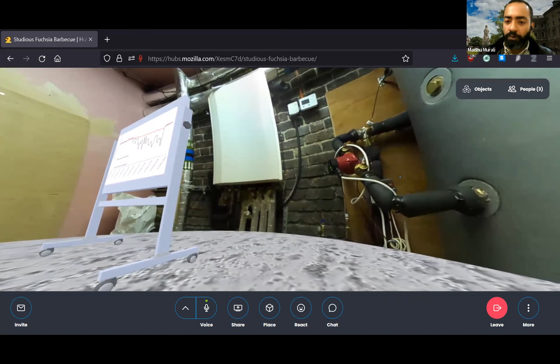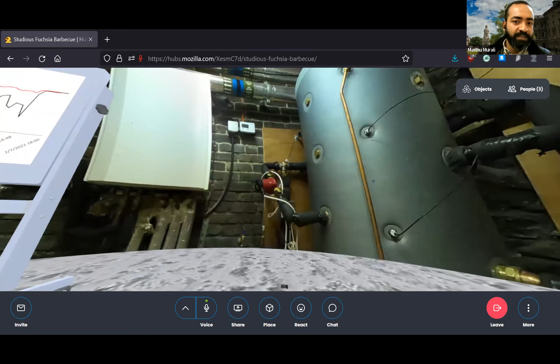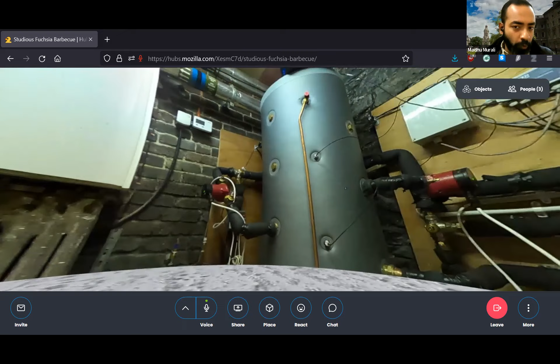Basically, what happens in this system is that the heat from the wastewater is always absorbed and put into the buffer tank. But the buffer tank isn't a completely necessary part of the system. It was more of a trial in this case to see whether the buffer tank improved the situation and provided more energy overall. It did provide quite a bit of energy, and we're quite happy with how it worked. But the system could also operate without the buffer tank, whereby the cold water coming into the system is heated through the heat exchanger, goes into the heating interface unit directly, is mixed in and goes through to the kitchens.